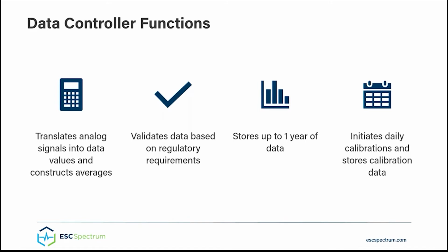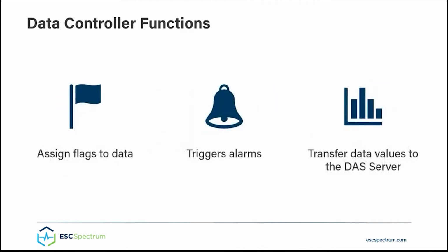It initiates the daily QA calibrations, which involves running through the required calibration sequences and storing the resulting data. The controller assigns flags to the data to mark it as in calibration, in maintenance, startup, shutdown, and so on. The flags are used to automate the identification of data as valid or invalid. The controller triggers alarms that provide alerts to emissions exceedances and operational conditions. And finally, the controller continuously transfers the data to the DAS server via the plant's network. Now let's take a look at the key functional areas of a DAS.